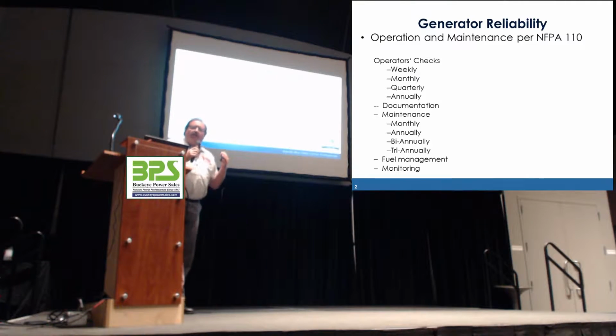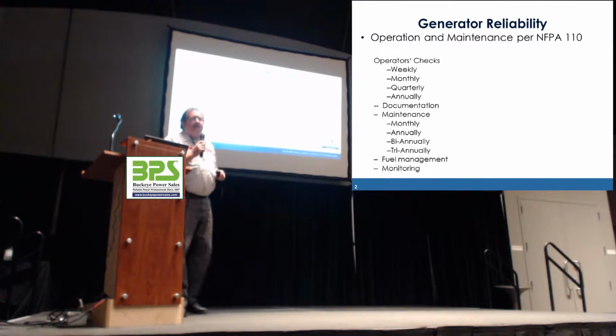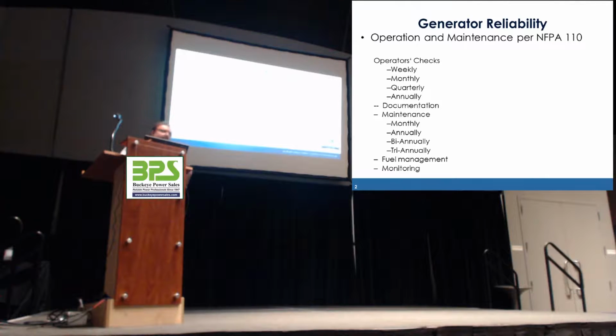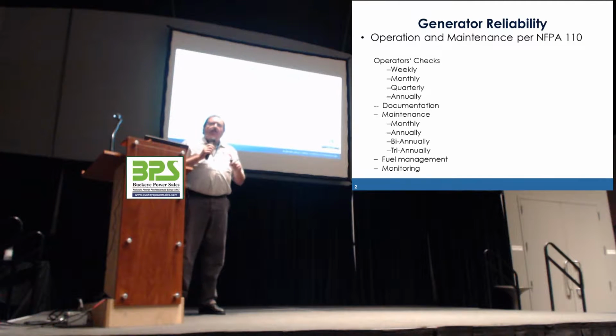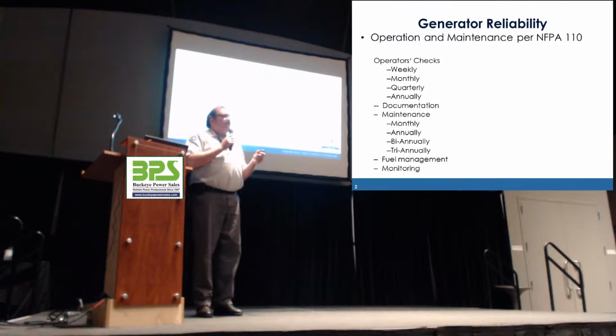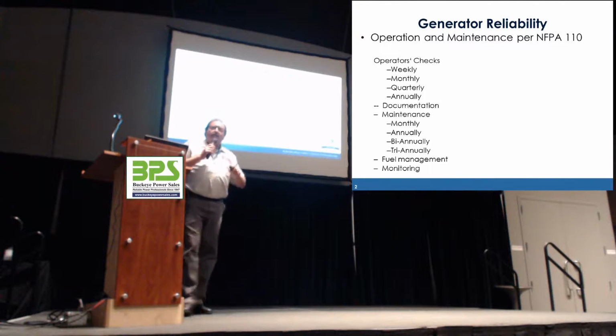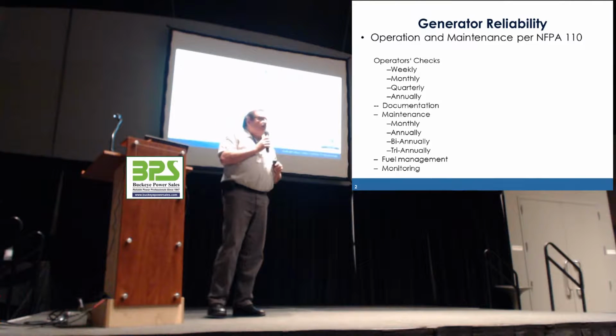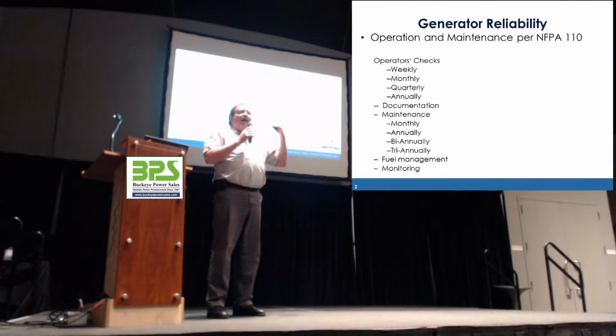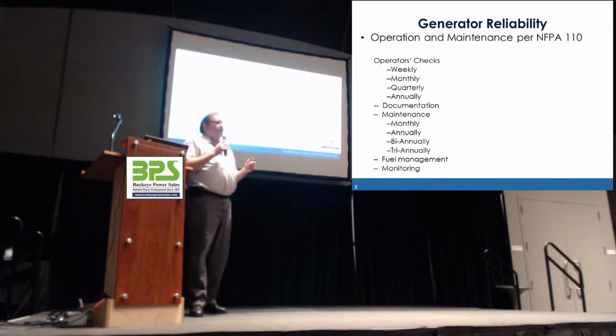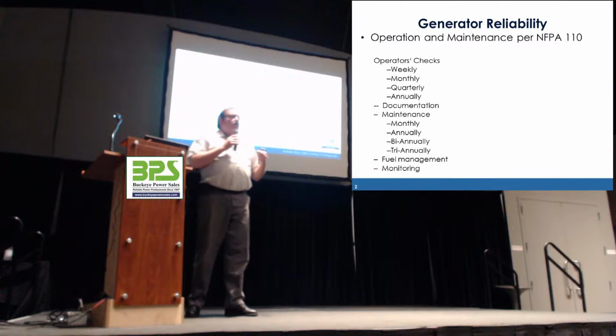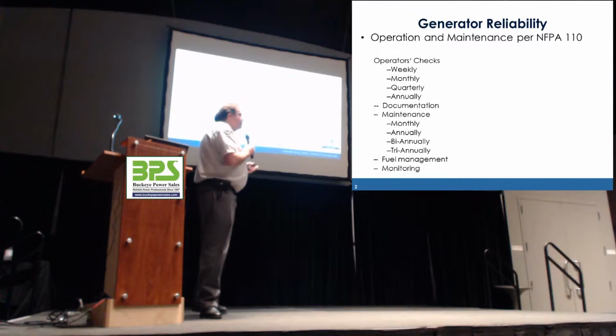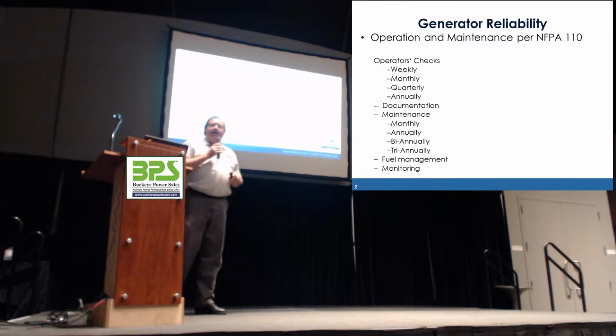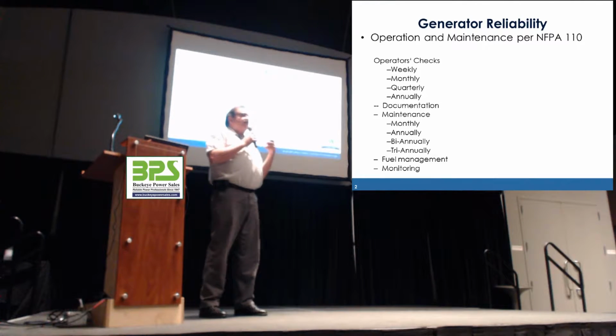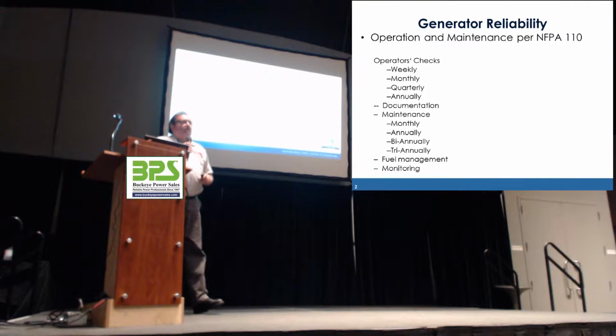So the principle that we based this on is NFPA 110, which is the code that governs life safety. And you say, well, this is IT, this isn't life safety, but most of you here would probably say that your equipment and your business is more important than life safety. The reason we used NFPA 110 is it happens to be the highest written spec that we have on what our maintenance should be. And everybody's goal is the same, uptime. You want that reliability, to try to get that 99.99% uptime. And to get there, we have to do certain things on our end to assure that.